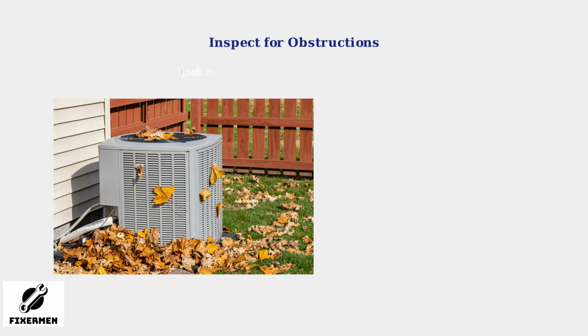Before starting any work on your American Standard Silver 16 AC unit, safety is paramount. Always disconnect the power to the unit at the breaker to avoid electrical shock. Next, inspect the outdoor fan for any visible obstructions. Common issues include leaves, debris, or ice that can block the fan blades and prevent proper operation. If you find any obstructions, carefully clear them away from the fan blades. This simple step can often resolve the issue without further repairs.